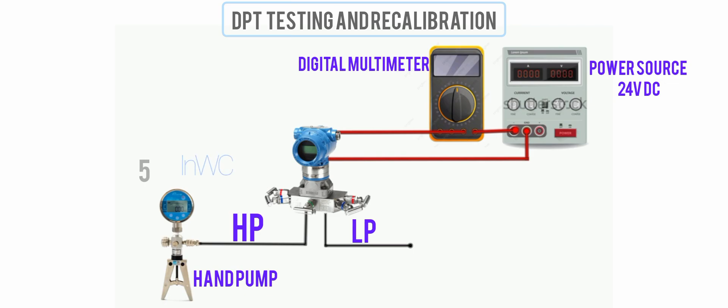We begin by applying the desired pressure input values from the calibration table to the high input on the flow transmitter and record the output current measured for each input value. If the output currents measured are outside of the acceptable ranges as established by your company, then the transmitter must be recalibrated using the zero and span adjustments.